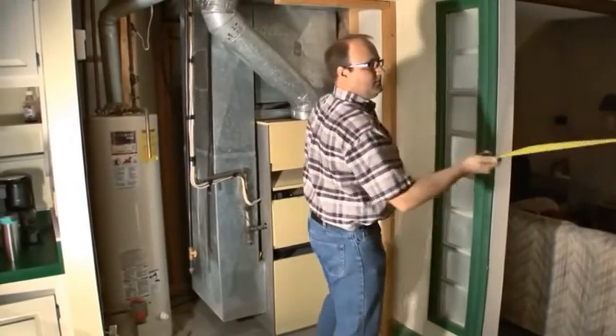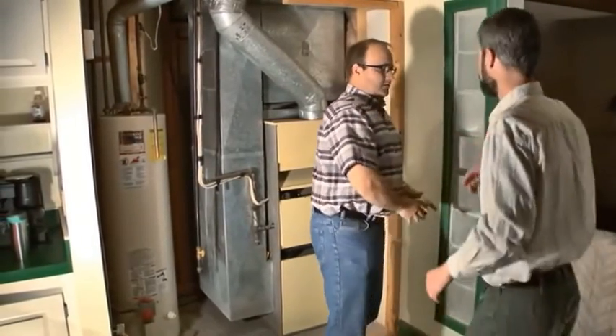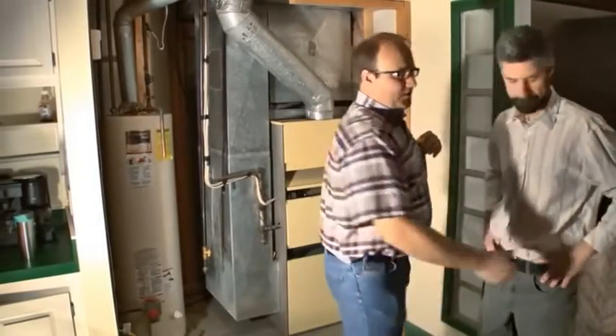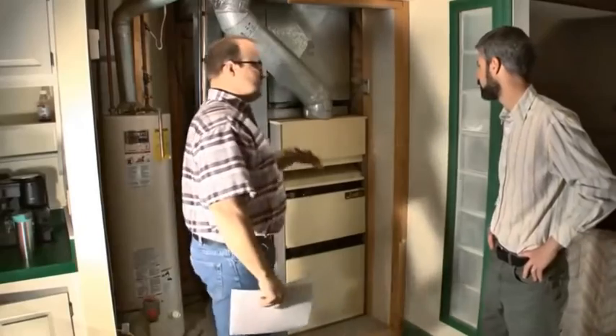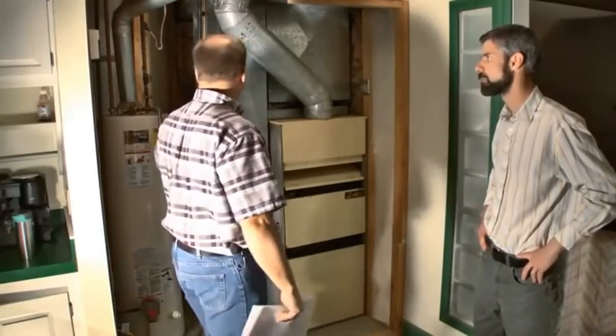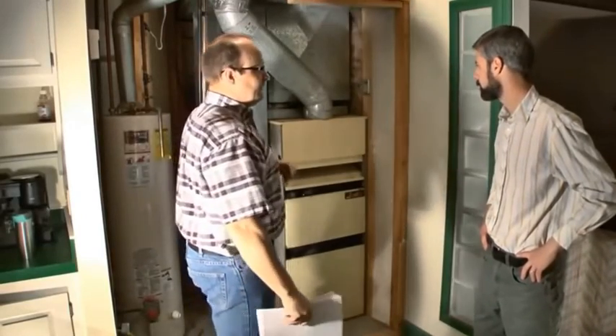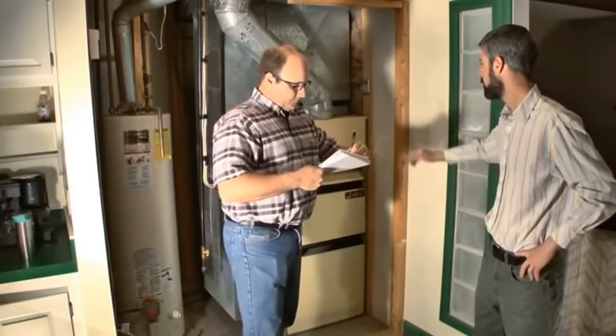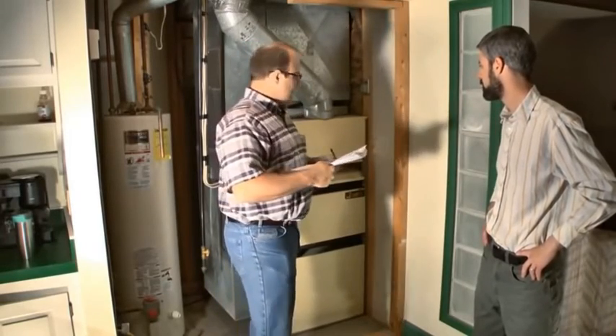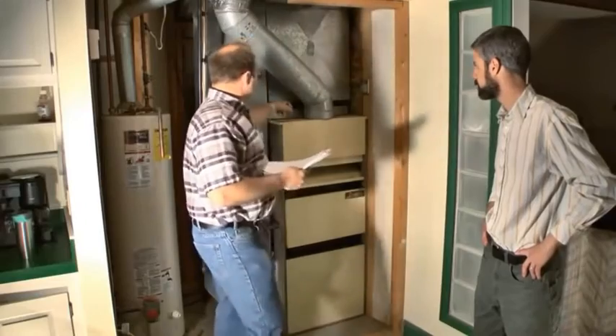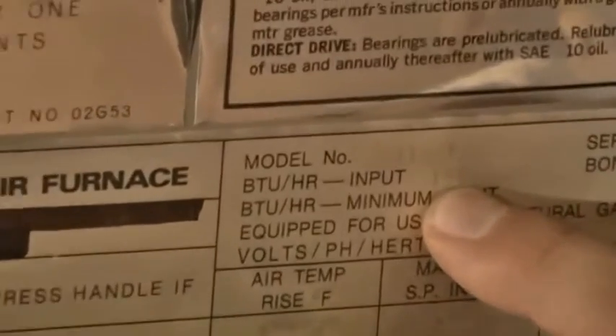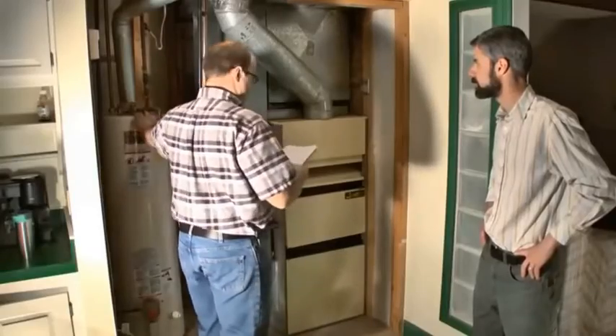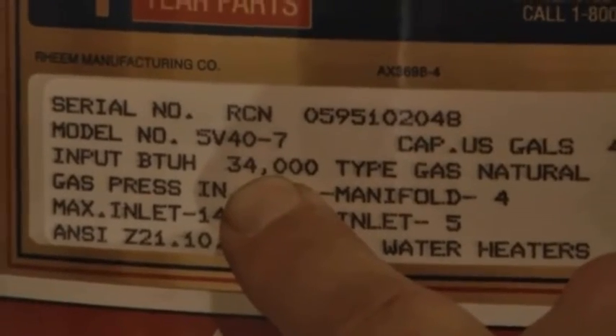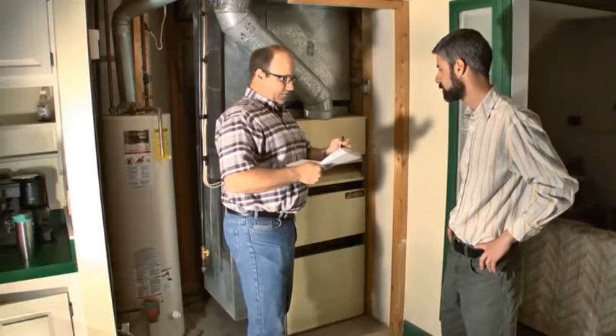Okay. Deal. So what are we measuring? Well, I'm trying to figure out how much volume we have in this room so that I can determine if there's enough combustion air supplied to these two appliances, this water heater and this furnace here. So how do we know how much these two appliances need? Well, what I did is I looked at it: this is a 138,000 BTU furnace, and this is a 34,000 BTU water heater. So total I need 172,000 BTUs of fuel input.